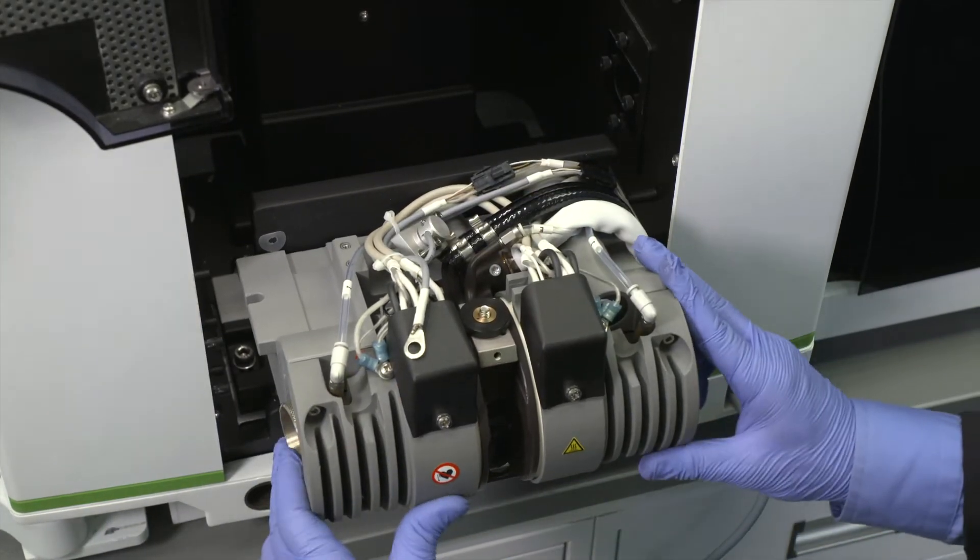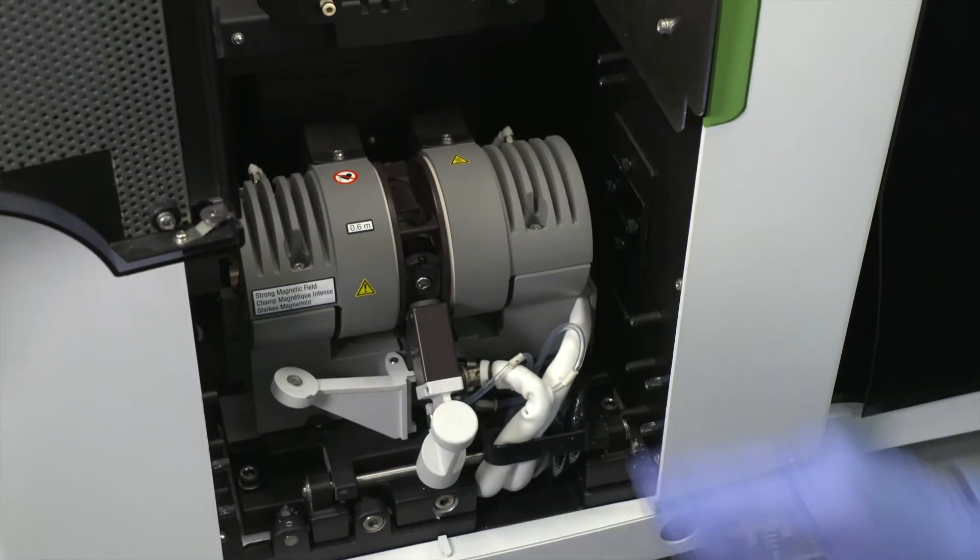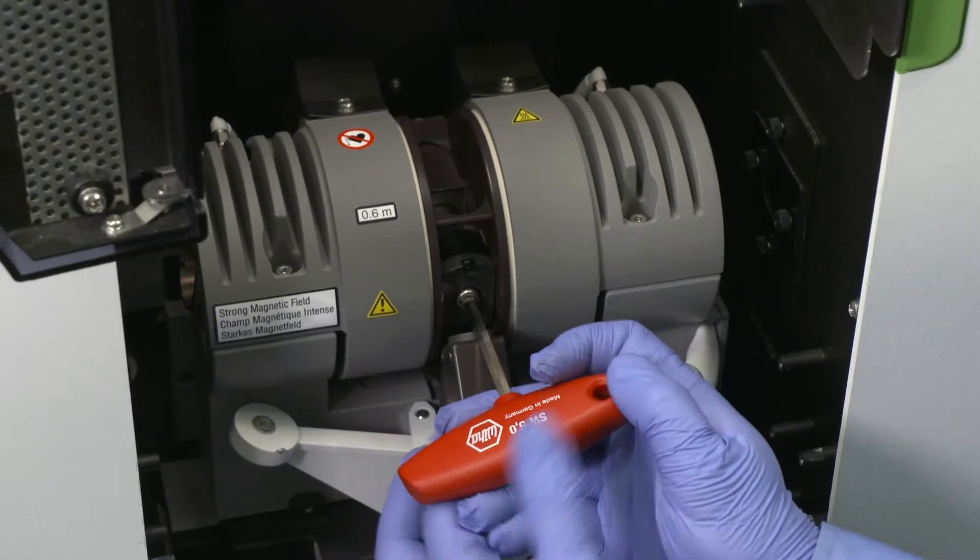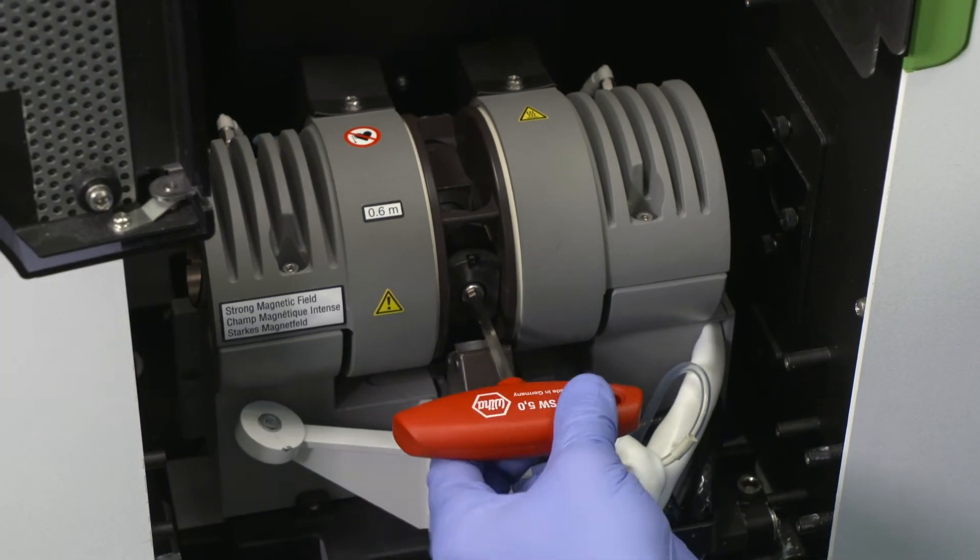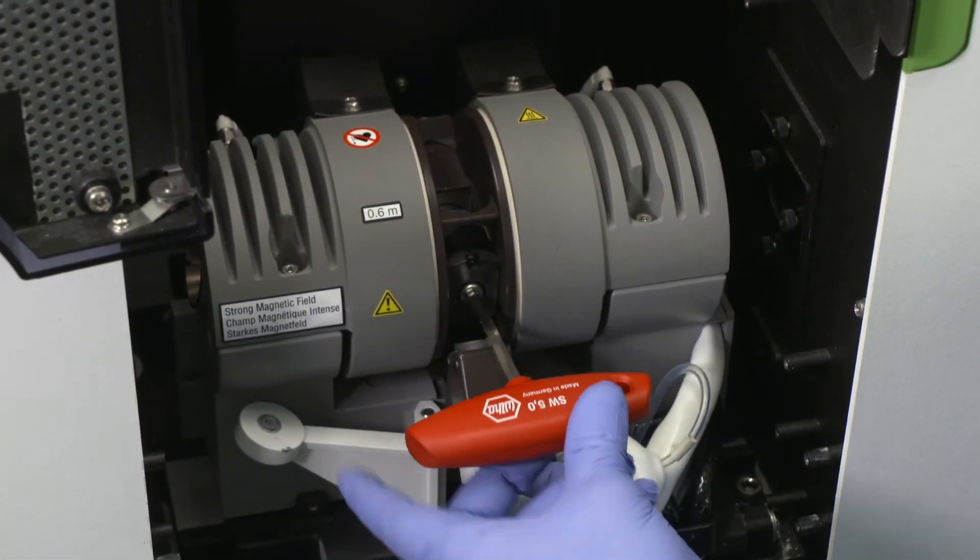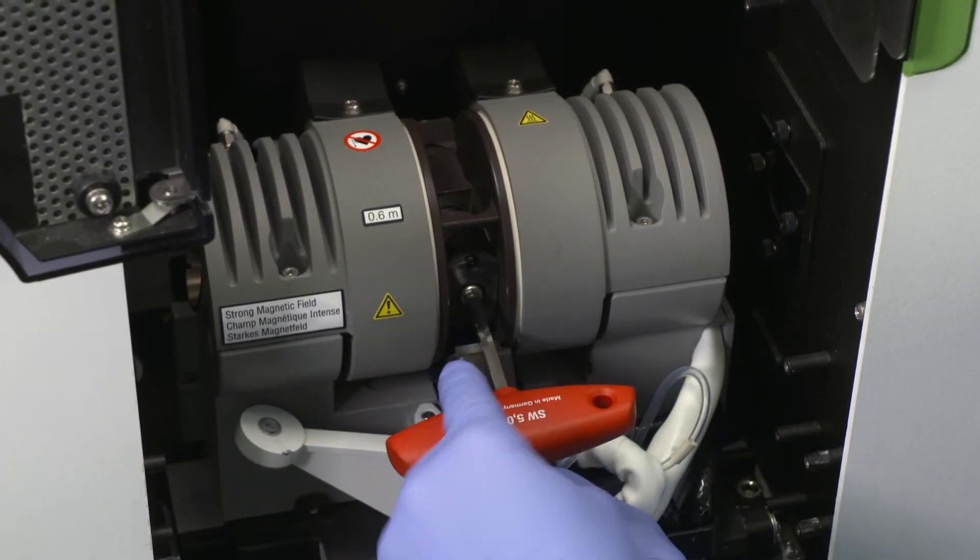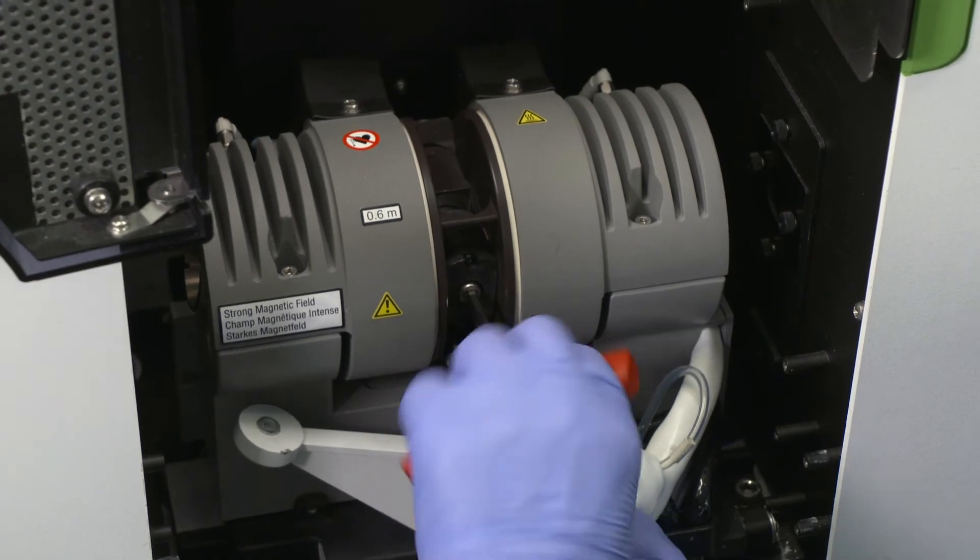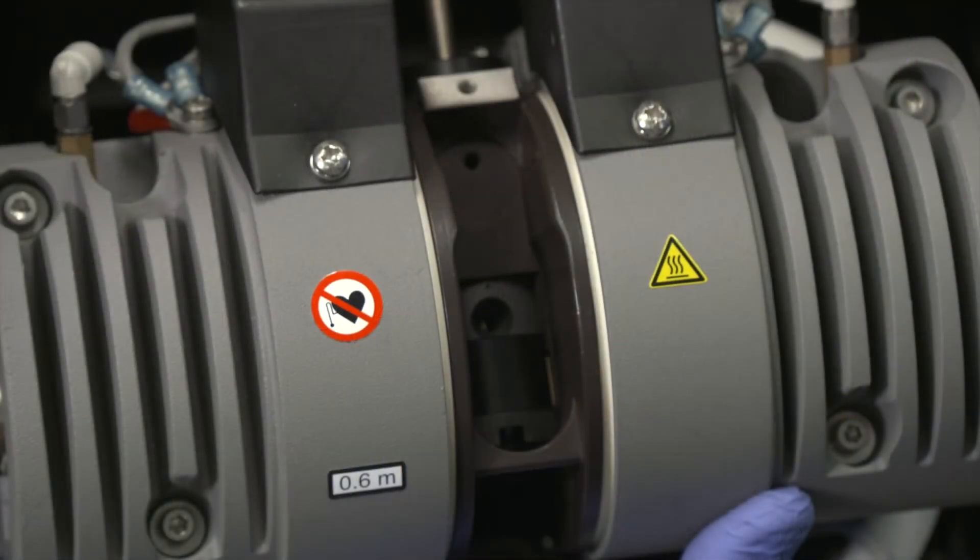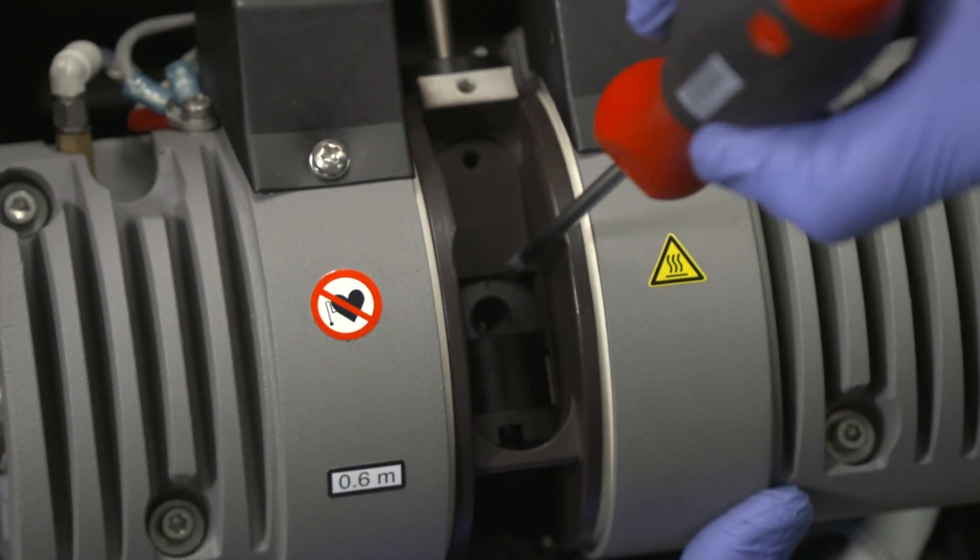Tilt the graphite furnace back into its original position. Then use the hex driver to screw the bolt into the threaded cylinder and push the contact into the contact housing. Do not use excessive force to push this contact into the housing as it may shatter the contact. If there is substantial resistance, check that the parts are aligned correctly. Screw in the bolt until the contact is flush with the contact housing.